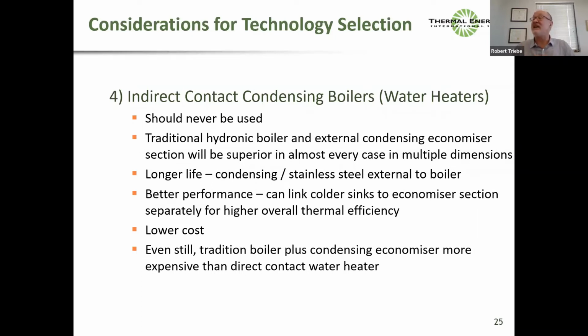And then there's an indirect contact condensing boiler. So now we've got the flame and the combustion gas on the outside of the tubes, but we've got cold water going in the tubes. And so we're condensing on the outside of those tubes. I've been looking at this for some time, and I'm going to make the bold statement they should never be used. And I'm going to say that because a traditional hydronic boiler, if it's not a condensing hydronic boiler, lasts like 30 years, it lasts for a long time, and an external condensing section will be superior in almost every case. Buying a condensing boiler versus a traditional boiler with a condensing stage separate, there's no comparison.